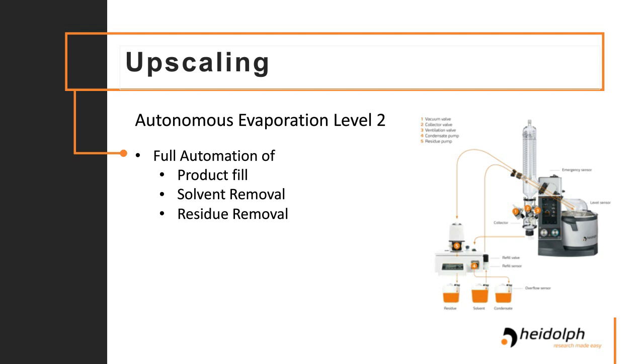With a very low liquid level, you gain the highest evaporation rate per minute, for example, and this can be ensured with these automatic modules that can be sensor controlled, or where you can set specific time frames for refilling small quantities into the evaporation flask.